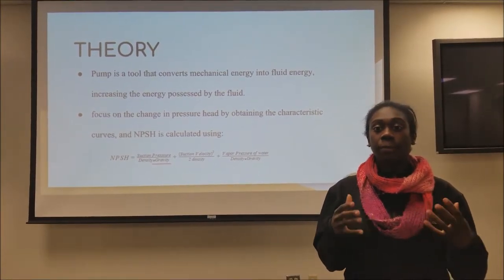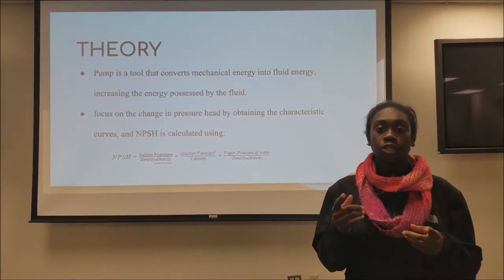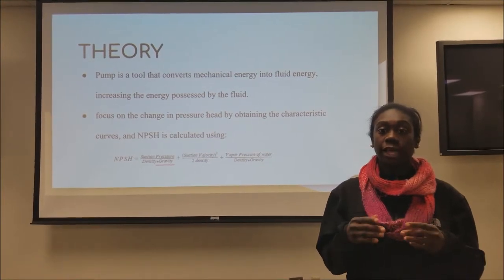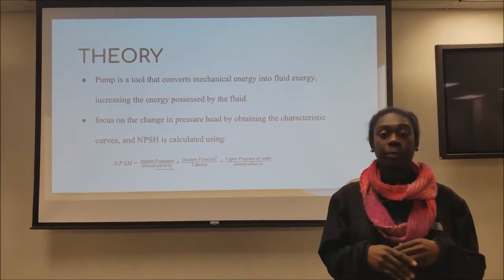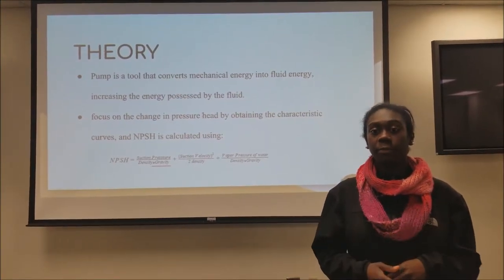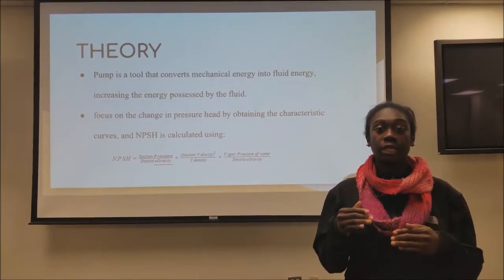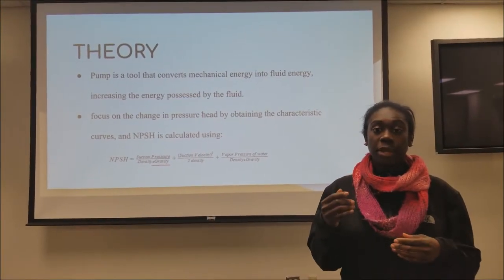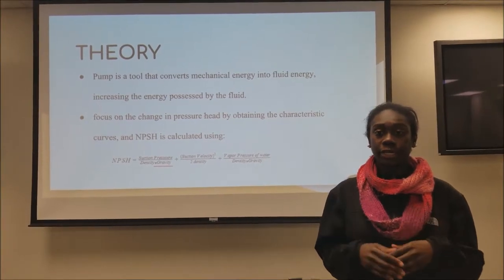Connecting pumps in parallel increases the pumping capacity of the system. Two pumps can be connected in parallel so that half of the flow passes through one pump and the other half passes through the second pump. When the two pumps are in parallel, the total head increase remains unchanged, meaning the flow rate is increased.